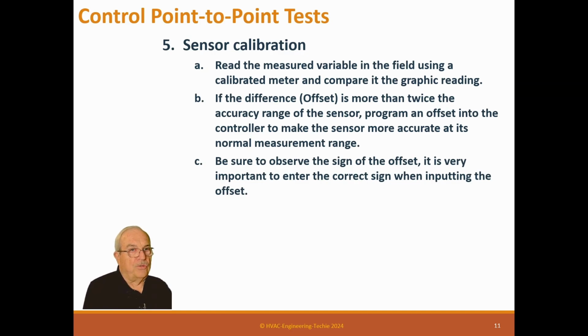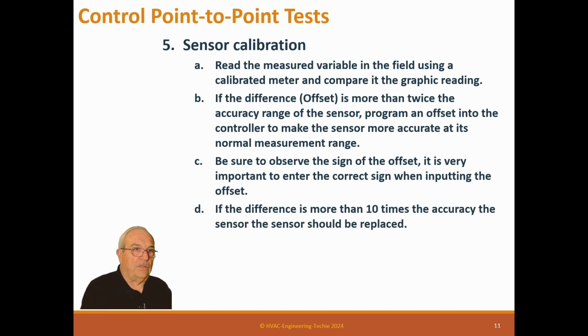Be sure to observe the sign of the offset. It is very important to enter the correct sign when inputting the offset. If the difference is more than 10 times the accuracy, the sensor should be replaced because it's too much. It's way out of range.